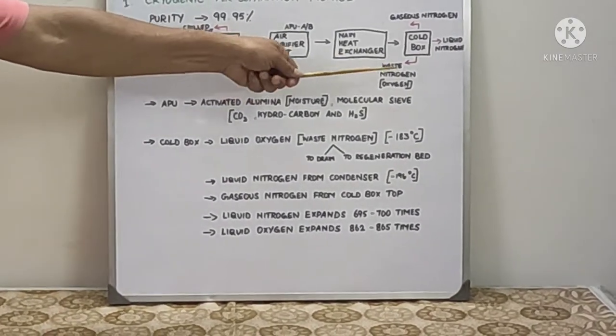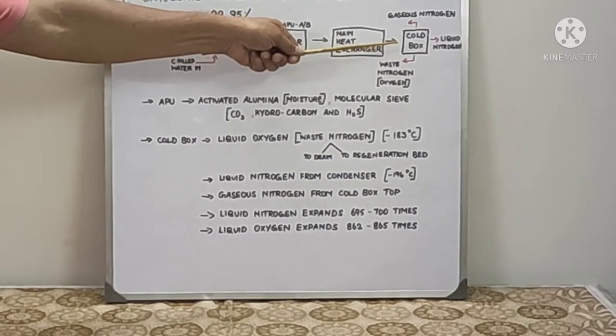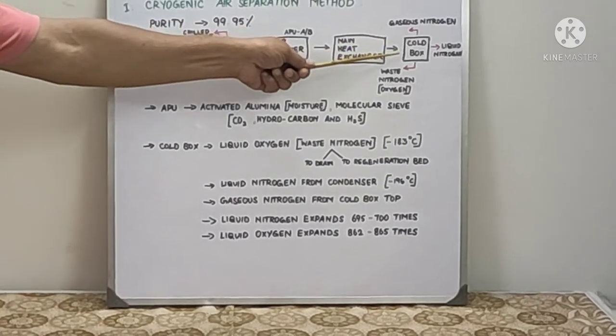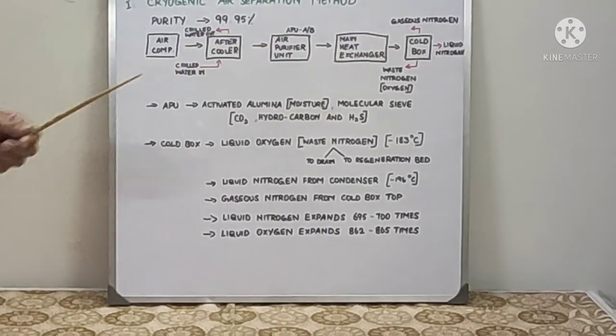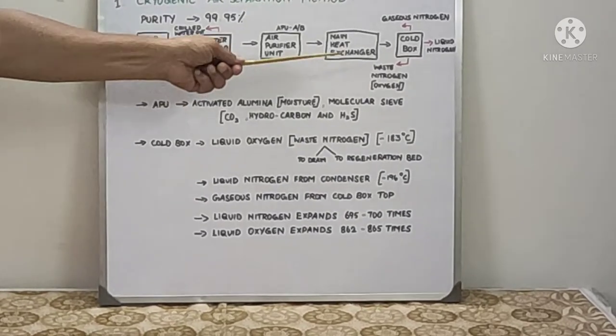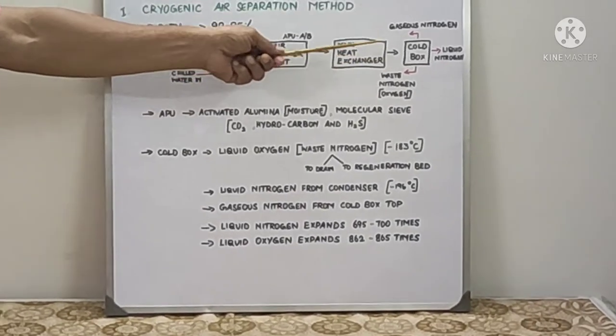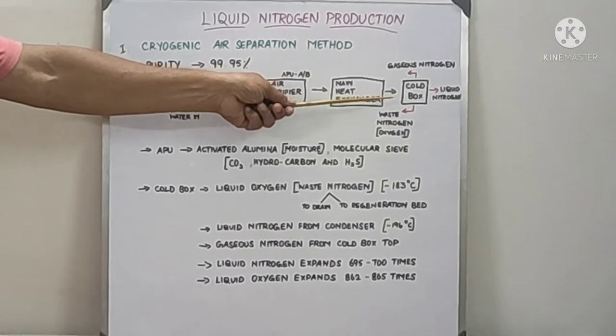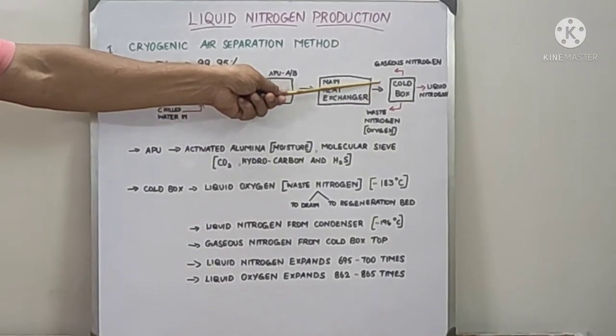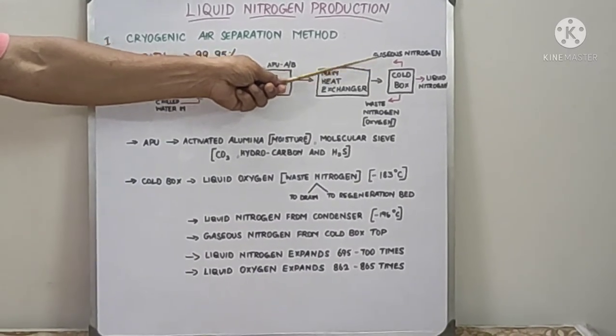In the cold box, we have two condensers and high pressure tower. After heat exchanger, if you want only liquid nitrogen, you will have expansion turbine. If you want gaseous nitrogen more, then you will have cold expander turbine and cold booster also.